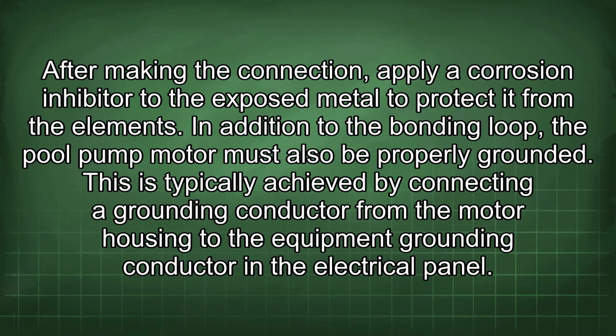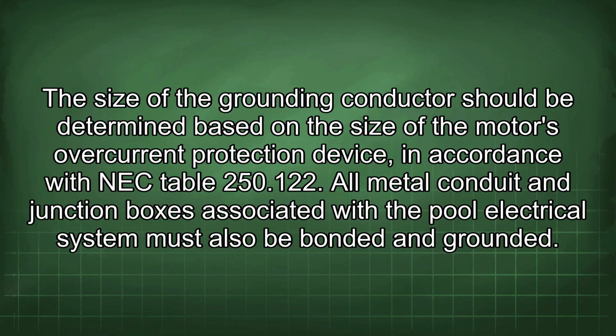In addition to the bonding loop, the pool pump motor must also be properly grounded. This is typically achieved by connecting a grounding conductor from the motor housing to the equipment grounding conductor in the electrical panel. The size of the grounding conductor should be determined based on the size of the motor's overcurrent protection device, in accordance with NEC Table 250.122. All metal conduit and junction boxes associated with the pool electrical system must also be bonded and grounded.